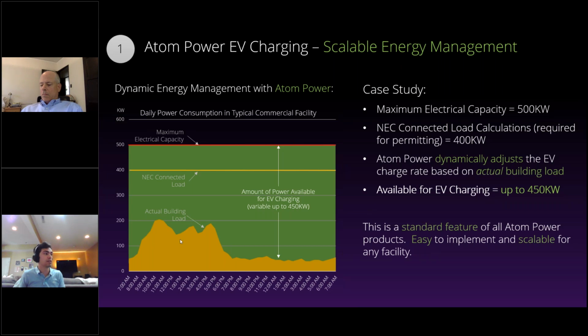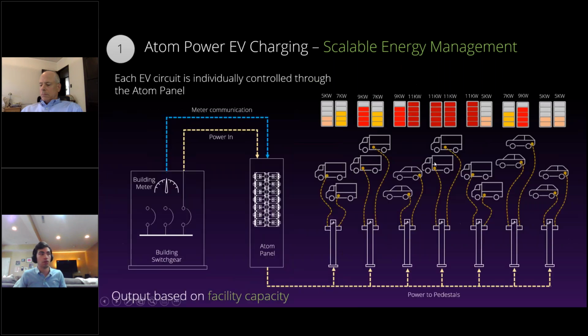You might have a lot of usage between 9 and 5, but after that your usage goes down. So even though your connected load shows 400 kilowatts all day long, we know it's not really running that high, and it's hard to see that unless you have some kind of meter upstream. So what we can do is place a building meter upstream in the building switchgear, ahead of our panel, so our panel knows all of the loads downstream.